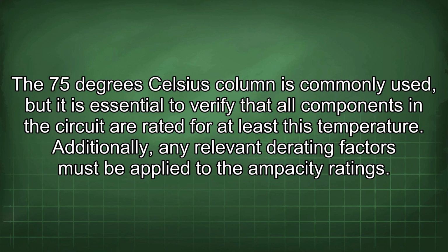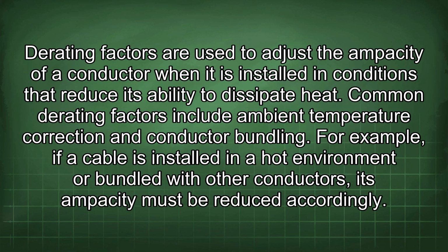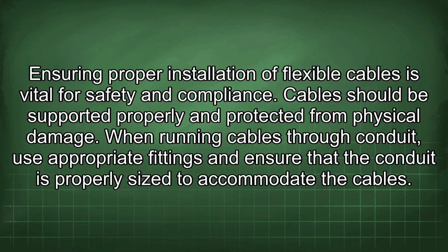Additionally, any relevant derating factors must be applied to the ampacity ratings. Derating factors are used to adjust the ampacity of a conductor when it is installed in conditions that reduce its ability to dissipate heat. Common derating factors include ambient temperature correction and conductor bundling. For example, if a cable is installed in a hot environment or bundled with other conductors, its ampacity must be reduced accordingly. Ensuring proper installation of flexible cables is vital for safety and compliance.